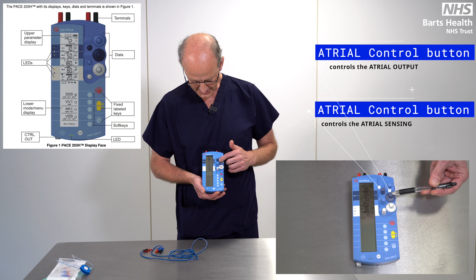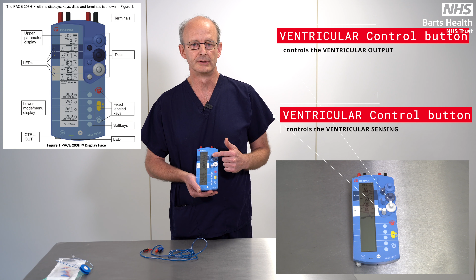The next two blue buttons, the darker blue buttons, are the atrial control buttons, and these control both the atrial sensing, that's the little button, and the atrial output, that is the big button. And you can see that helpfully the settings that they're set on are displayed adjacent to the buttons on the display. The next button as we move down through the heart is the AV delay button. That's the light blue button. And the bottom two controls here are the ventricular output, that's the large button, and the ventricular sensing is the smaller button there. So these are the main controls that you will need to adjust.